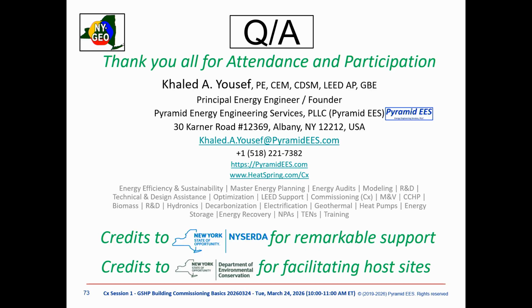Thank you for the good presentation. Some of the bigger issues - one of the bigger problems sometimes is that after a few years of installation, you have some facility managers that think they can be cheaper with gas if you have a gas backup and not run geothermal during the winter. Over time the temperature of the ground gets warmer and warmer, and they say the geothermal doesn't work for cooling. This is an issue we see. We presently have a 27-story building that this happened to after trying to salvage it.